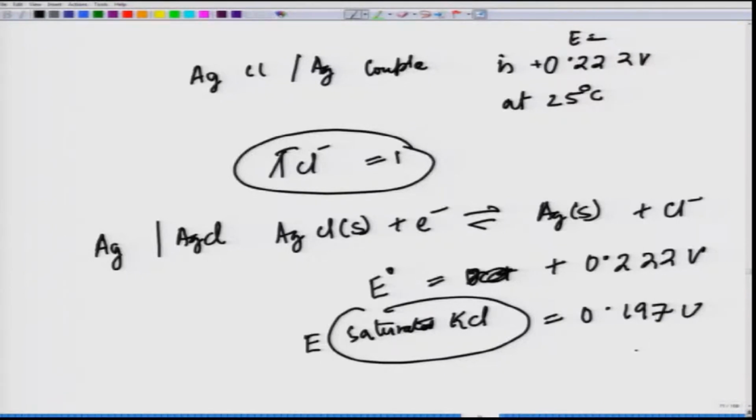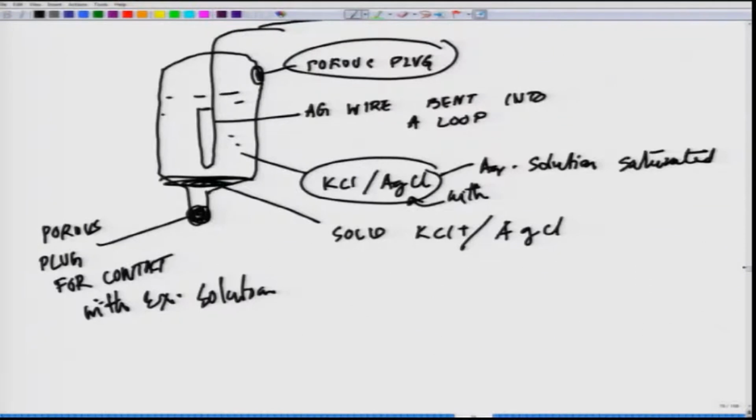The problem with reference electrode is that the porous plug becomes clogged. Okay. So, the porous plug, these are some of the practical problems you will come across. This plug is getting clogged. There are clogging problems, thus causing sluggish unstable electrical response. Some designs incorporate free flowing capillaries in place of porous plug. Other designs allow you to force fresh solution from electrode through the electrode analyte junction prior to the measurements.